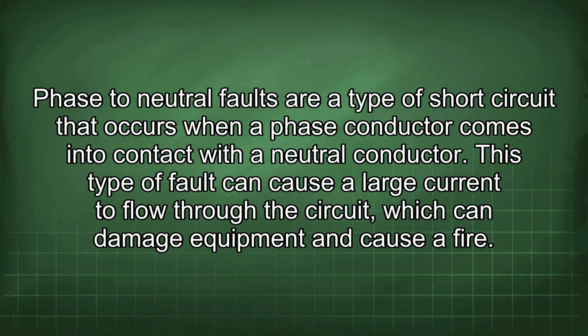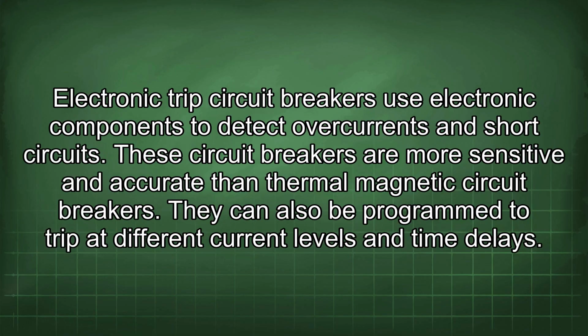Phase-to-neutral faults are a type of short circuit that occurs when a phase conductor comes into contact with a neutral conductor. This type of fault can cause a large current to flow through the circuit, which can damage equipment and cause a fire. Electronic trip circuit breakers use electronic components to detect overcurrents and short circuits. These circuit breakers are more sensitive and accurate than thermal magnetic circuit breakers. They can also be programmed to trip at different current levels and time delays.